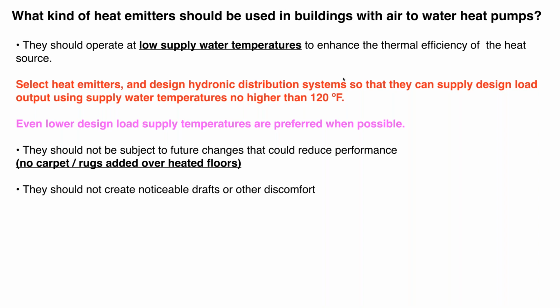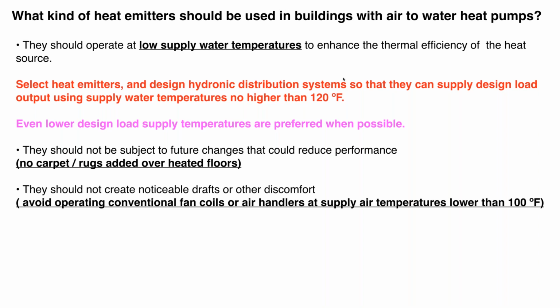Obviously, we want our systems to be as quiet as possible. We don't want drafts, okay? We want to be careful if you're operating any kind of fan coil or air handler at low heating temperatures. I'd suggest nothing less than 100 degrees Fahrenheit. And even at that water temperature, introduce that air very carefully into that space so that it doesn't directly blow on where somebody is sitting.